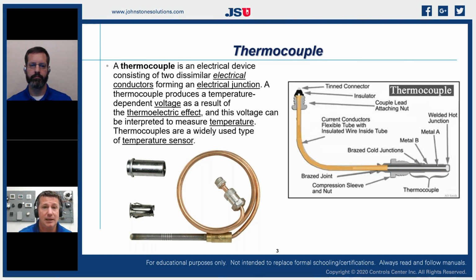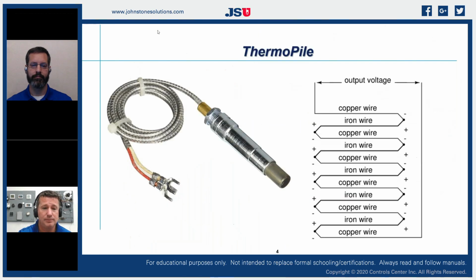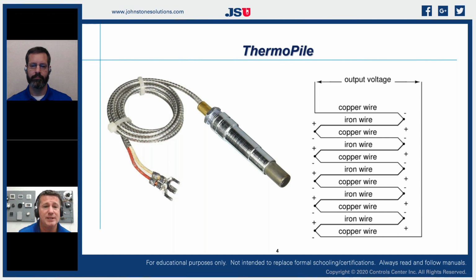I mean, we would have a switch to bring on our gas valve, which was our thermostat, and then we would have a fan switch that would bring on our blower to turn our blower on. But besides that, really, we didn't use a lot of controls. We used a thermocouple to hold our gas valve in. So what we did with that thermocouple is we just created voltage to hold a solenoid. And we found that if we needed more voltage, we just applied more thermocouples. And we put them in a series circuit so that we can increase the voltage.